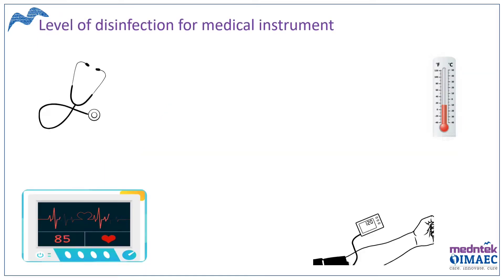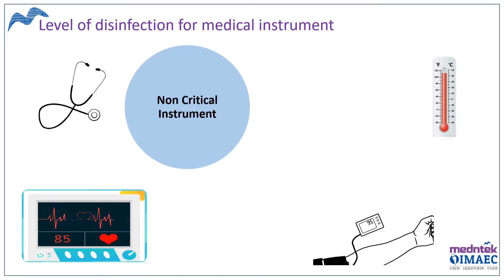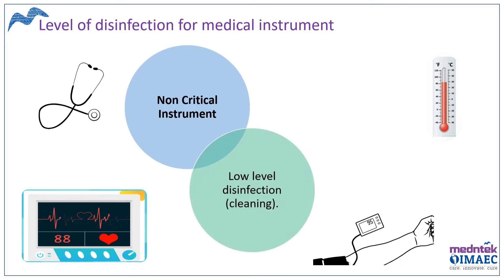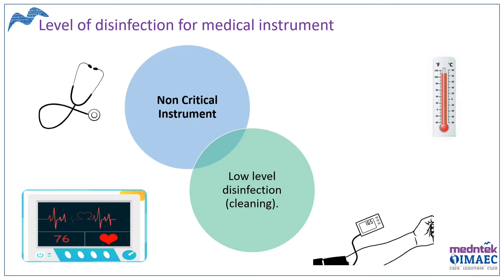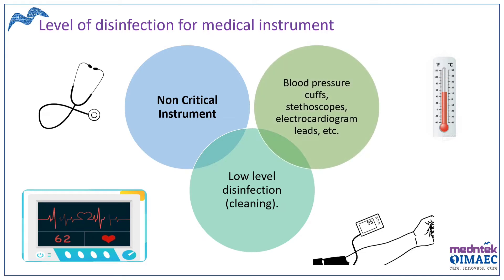The level of disinfection for medical instruments depends on the category of the medical device. Non-critical instruments require low level of disinfection as they come in contact with only the intact skin of the patient, which is already a barrier for pathogens. Examples of non-critical instruments are blood pressure cuffs, stethoscopes, and electrocardiogram leads.